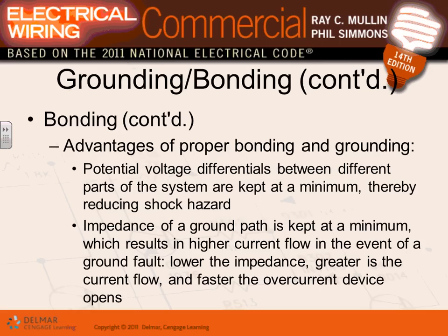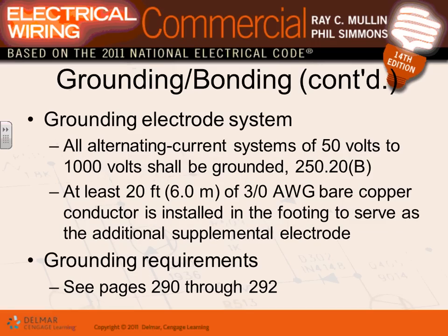So that's basically the bonding. Why we bond things: to minimize the shock, guys, and facilitate the operation of the overcurrent protection device. The NEC requires any system of 50 volts or over, all the way to 1000 volts, to be grounded, with very few exceptions. So in the building, you take a grounding electrode conductor and you tie it to one conductor in your system. That's called the grounding electrode conductor.